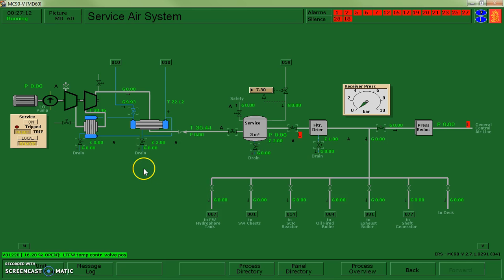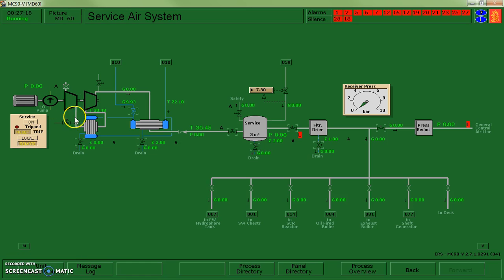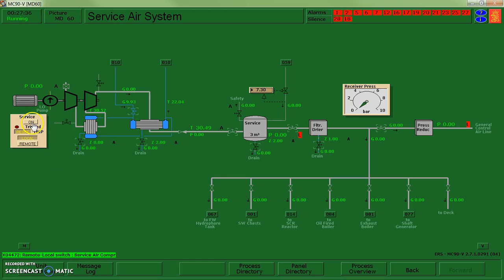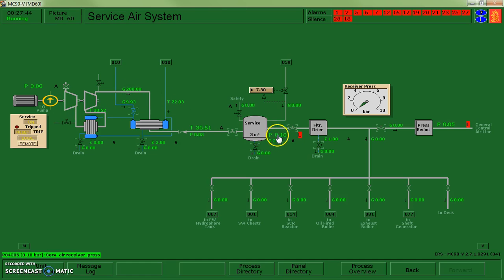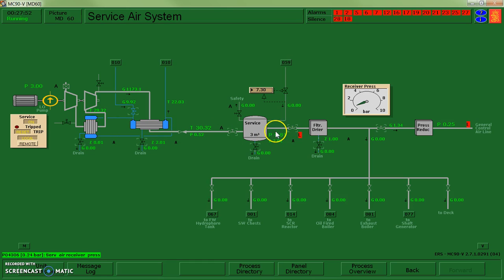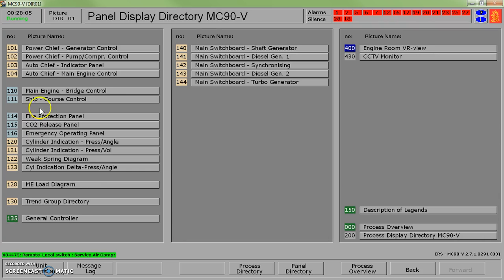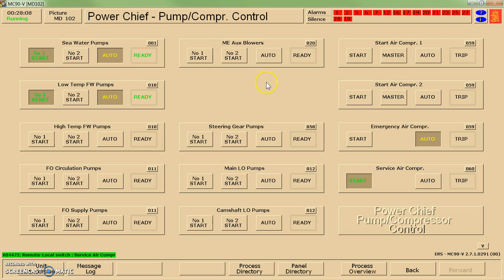My service air compressor is here. If I follow through my pathway, it comes through, I've got two stage compression, intercooler, after cooler, and then a pathway to get to my receiver and then a pathway after that into the general control airline. I'm just going to start it locally. The air compressor is on and we can see that my pressure is rising. I've got cooling water so I think this system is working pretty good. I'm going to switch this guy over to remote so that I don't have to be in charge of the on-off operation. I'll switch into remote, go to 102, and switch my service air compressor into auto mode.